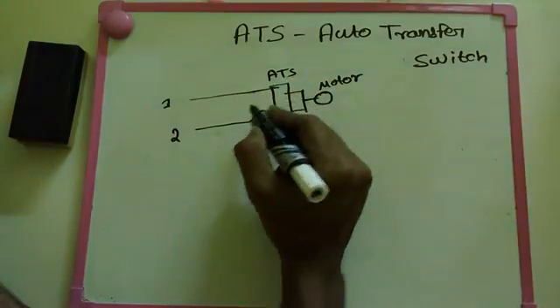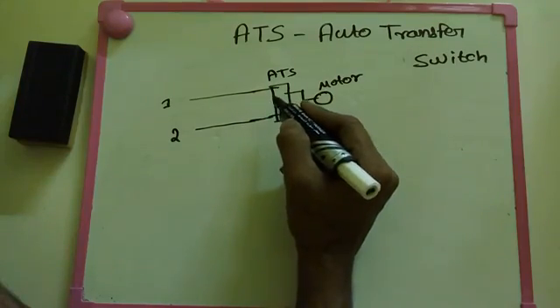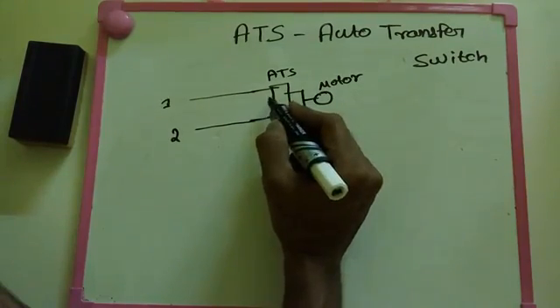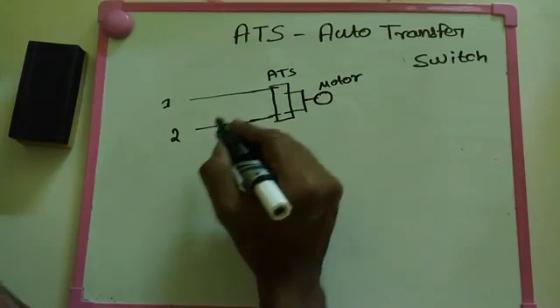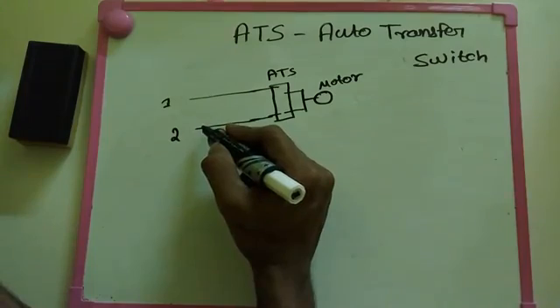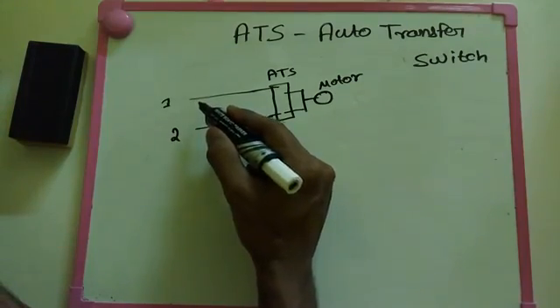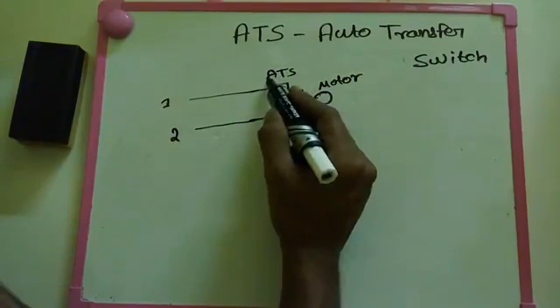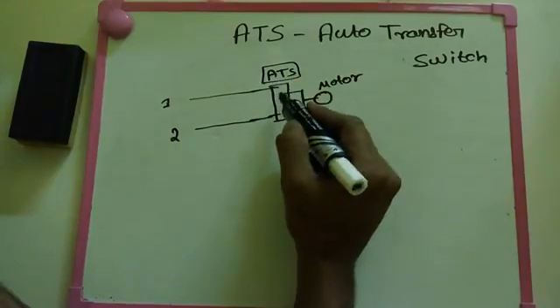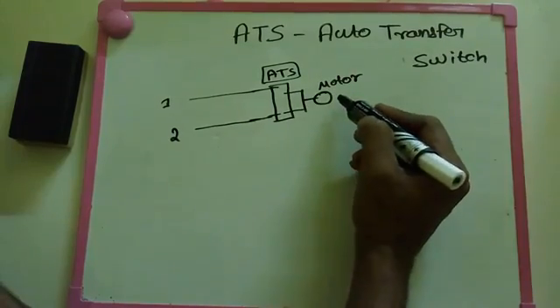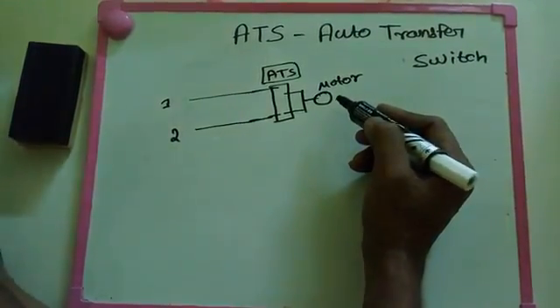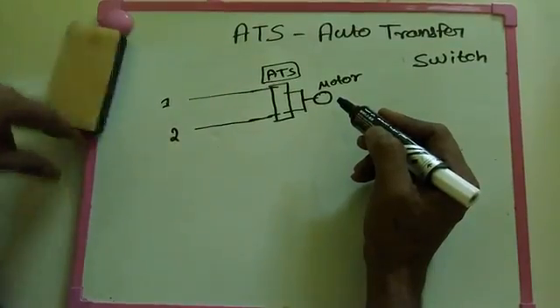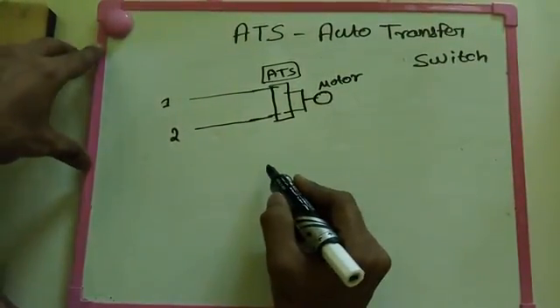So the motor needs to continuously run. This thing we need to make by using ATS. What's the function of this? An interlock will be placed here - that means the first one and second one don't operate at the same time. When the first one is switched on, the second one is switched off; when the second one is switched on, the first one is switched off. So any one of these two is switched on at a time. That's the main purpose of the ATS - to provide continuous power supply to the motor or any load.